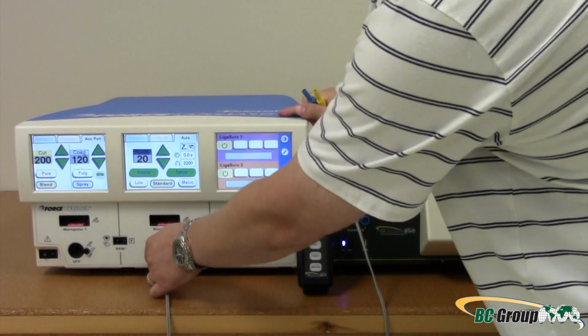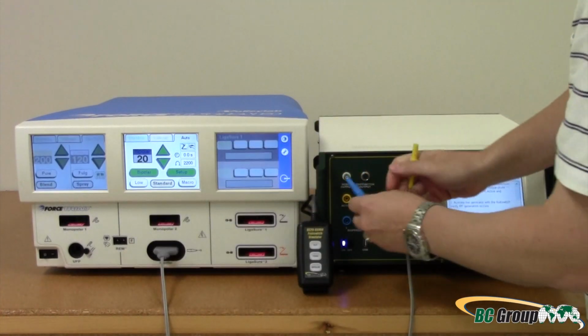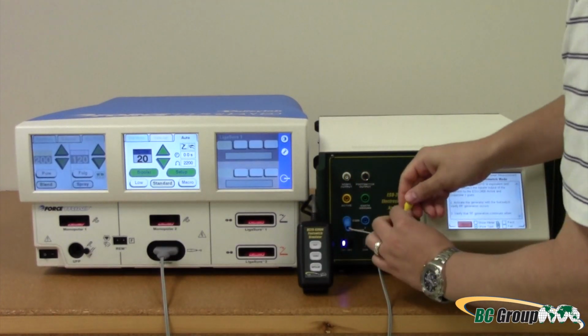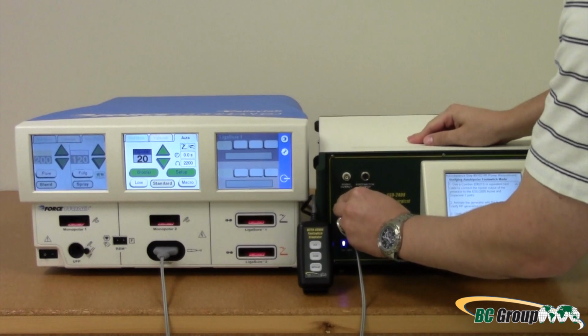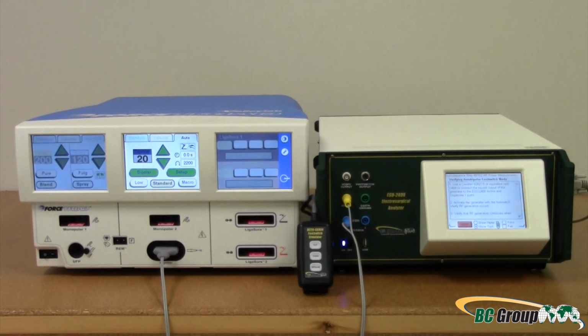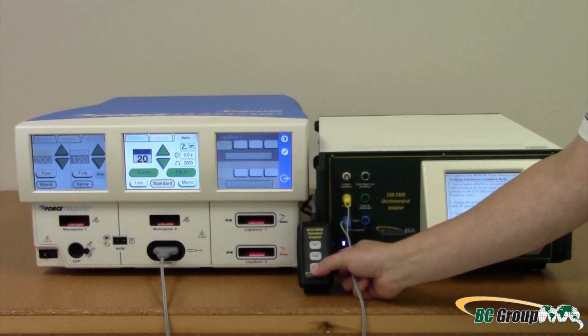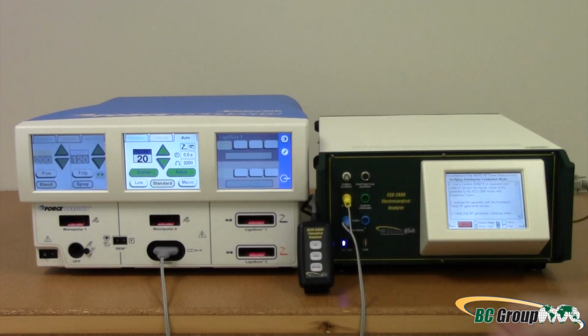Use the autobipolar lead to connect the bipolar output of the generator to the ESU-2400 active and dispersive 1 ports. Activate the generator with the foot switch or foot switch simulator. Verify RF generation occurs. Verify that RF generation continues when the foot switch is released.